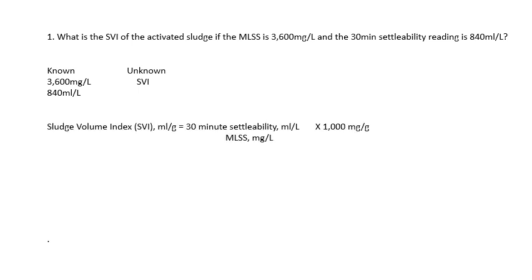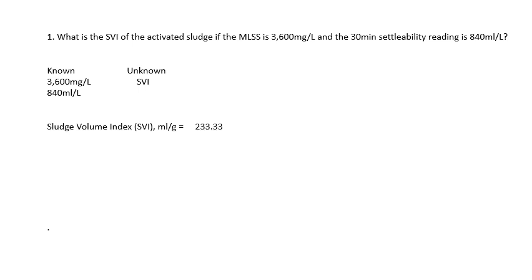Using the Sludge Volume Index formula, we plug our numbers in: 840 milliliters per liter divided by 3600 milligrams per liter, times 1000 milligrams per gram. Everything cancels out and you're left with 233.33 milliliters per gram.